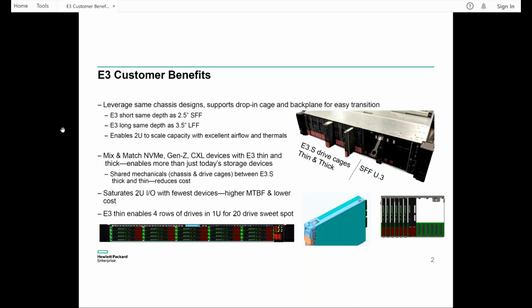Right. And also, we are probably past the world of being able to fill up the entire front end of a server with devices. Given the unconstrained TDP ramping of certain processors, we may have to put some big holes in the front of the server just to get enough air to cool the procs and the memory. Actually, it's not so much the processors anymore, it's the memory. The memory is starting to go really high in power. Yes.